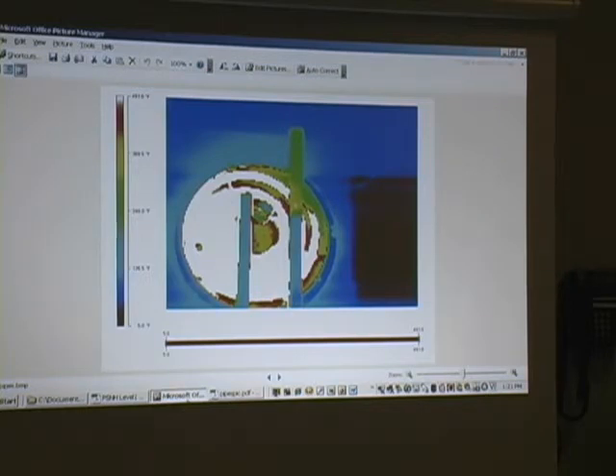When I look at the shiny part of the copper tubing, and I'm looking straight down, where's it reflecting? Straight up, just like a mirror. It's bright and shiny. So I'm pointing down. Any light or heat coming down from it is going to point right back at the camera. It's going to reflect. It's pointing at the sky. If I take this camera and point it, not at the sun, because there's a big dome over the camera, I point it straight up at the sky. And it's 104 degrees outside today.